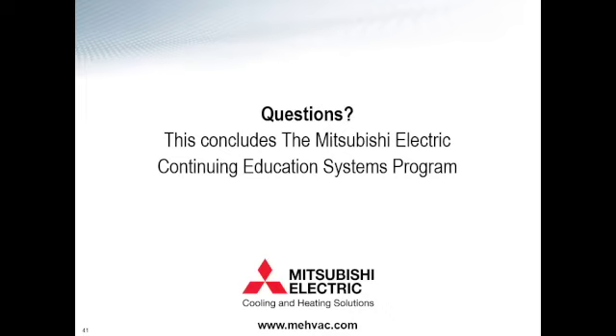Yes, it is possible, but it would not be directly. The way to think about it is the ERV is really going to be recovering that energy with some kind of energy recovery core. We can't supplement that core. But what we can do is provide heating and cooling or excess heat to a coil in the ERV if required. So we have the ability to provide, instead of an indoor unit, purely just a coil that can be placed in any kind of unit that you'd like. It can be placed in the ERV. It can be placed right into a duct run.